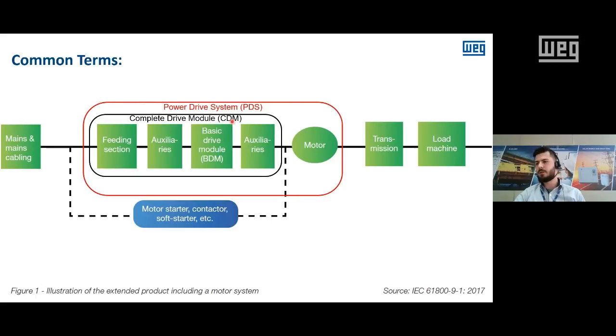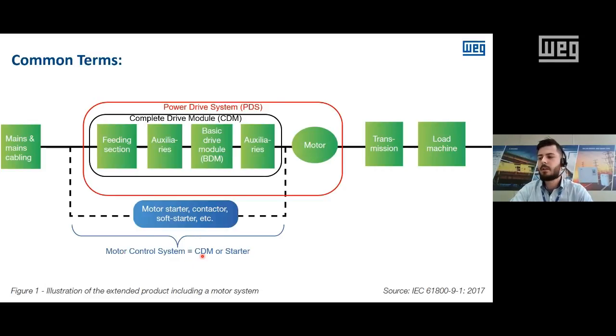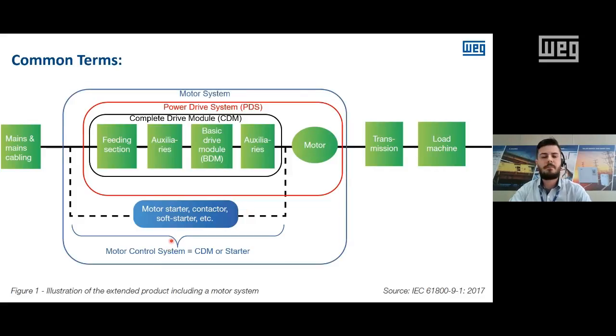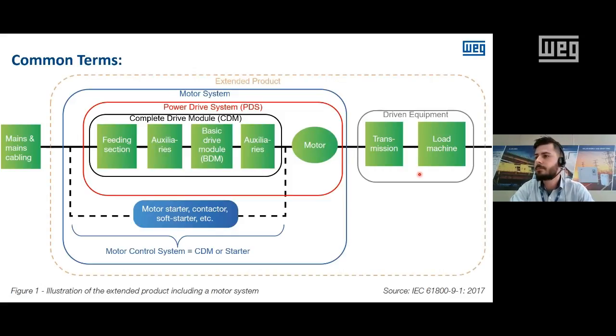If we consider a complete drive module plus the motor, we have the power drive system, which we call PDS. Similar to a CDM, or even including the CDM, we have what we call the motor control system. A motor control system is either a CDM or another kind of starter. It could be a soft starter, a direct online starter, and so on. So this is called the motor control system. And if you have a motor control system plus a motor, you have a motor system. After the motor, we have the transmission and load machine, which together are the driven equipment, the equipment that the motor is coupled to and is going to drive. And all of this, the CDM or the motor control system, the motor itself, and the driven equipment, is called the extended product.